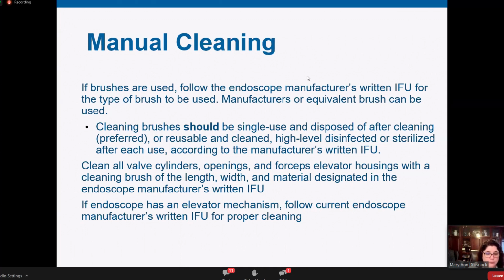So that's important to make sure that we're decontaminating and reprocessing those appropriately, making sure we're doing everything right with that forceps elevator on our duodenoscopes, following the IFU from our scope manufacturers for that, and the manipulation and flushing of it and everything, brushing at all steps along the process. That's very important to make sure that we're getting those types of scopes clean.